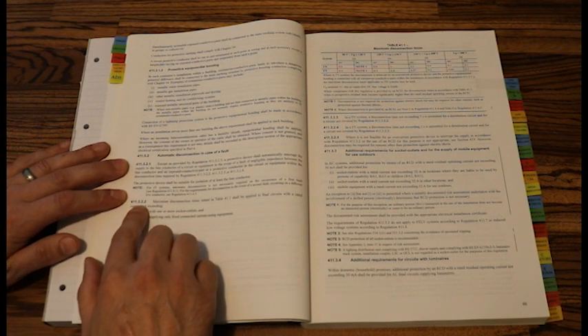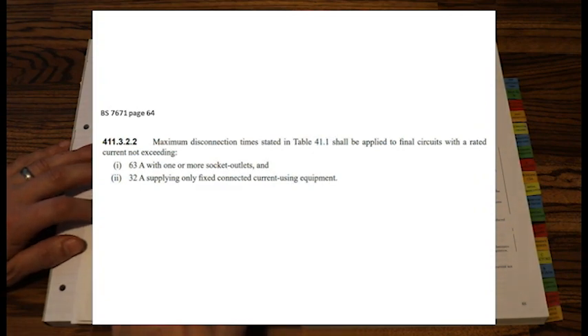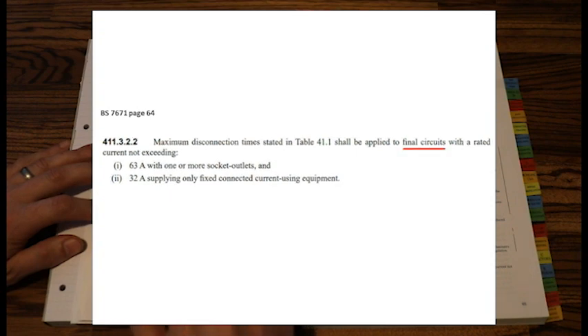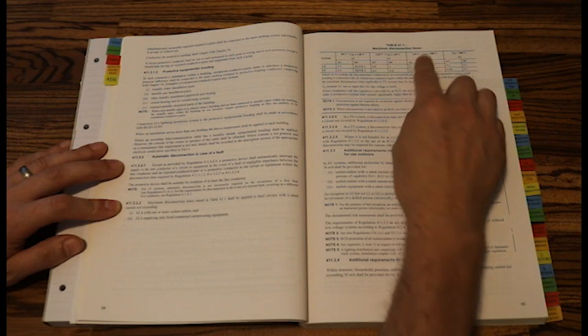This table applies if we first read this regulation. So 411.3.2.2 says maximum disconnection time stated in this table shall apply to final circuits with a rated current not exceeding 63 amps for a socket outlet or 32 amps for fixed current using equipment. Our question is for a distribution circuit. It's not a final circuit. So we don't use this table 41.1.